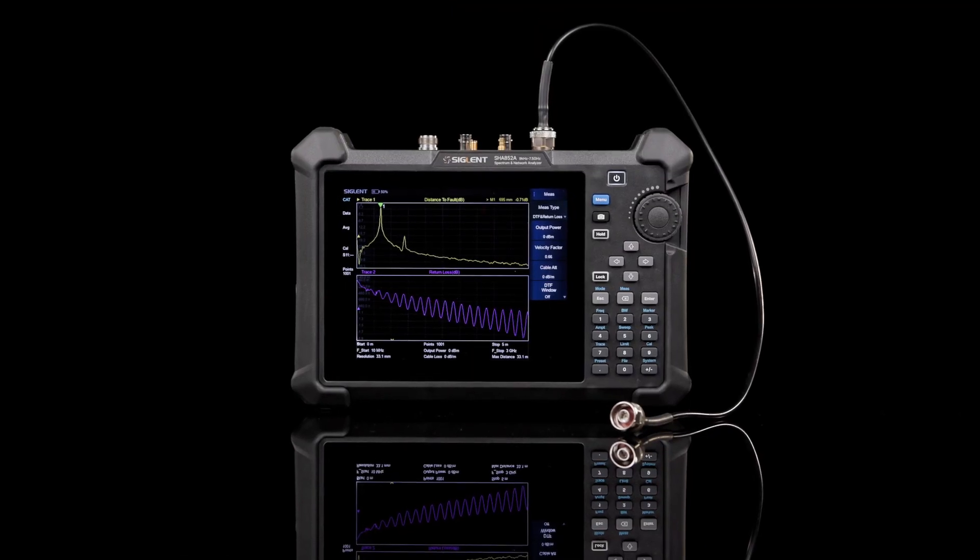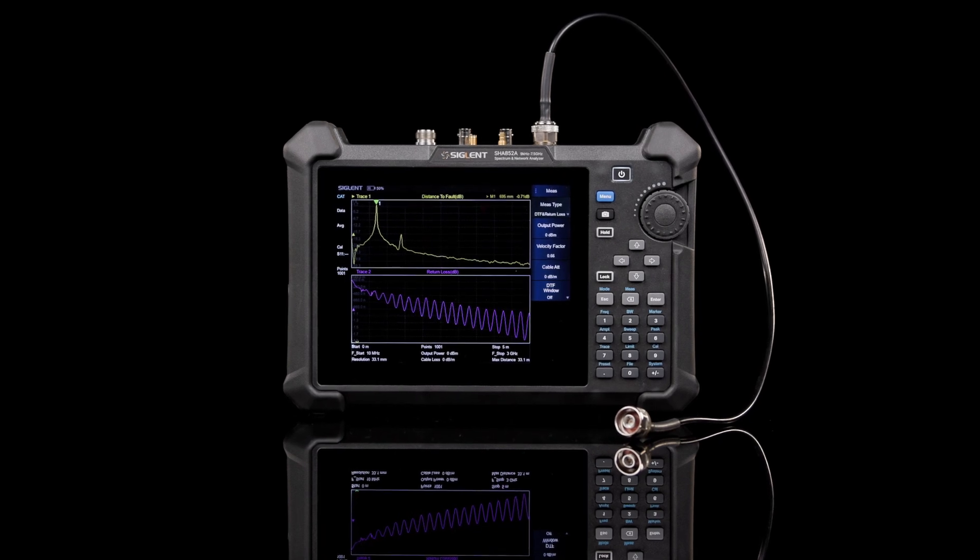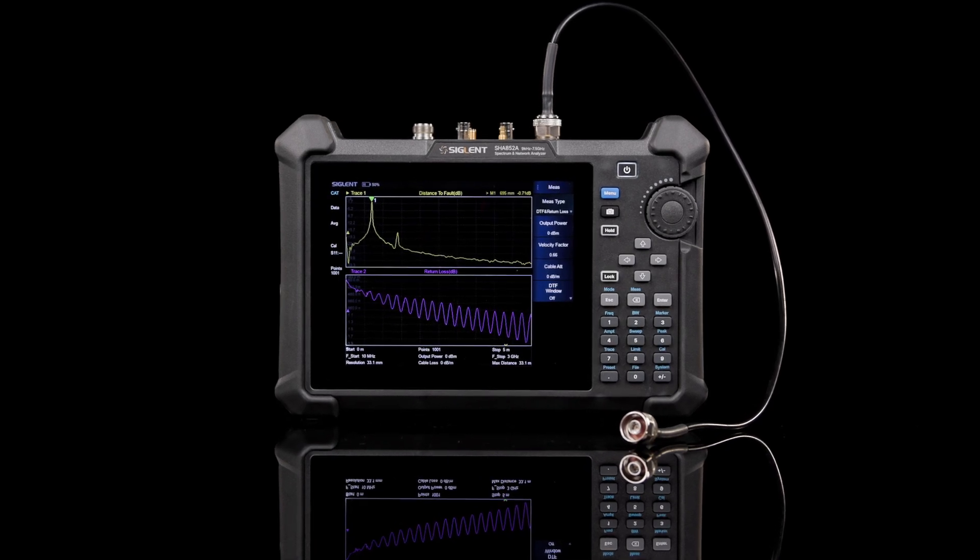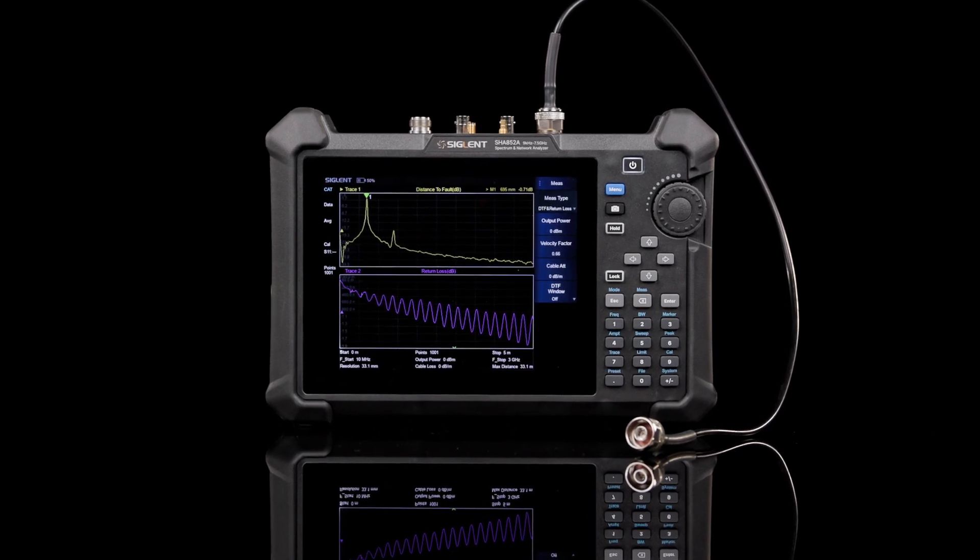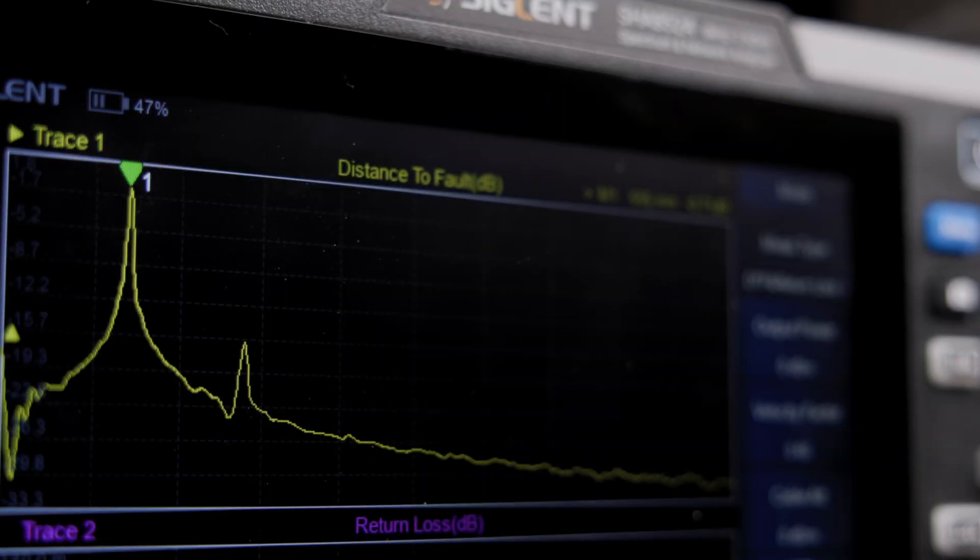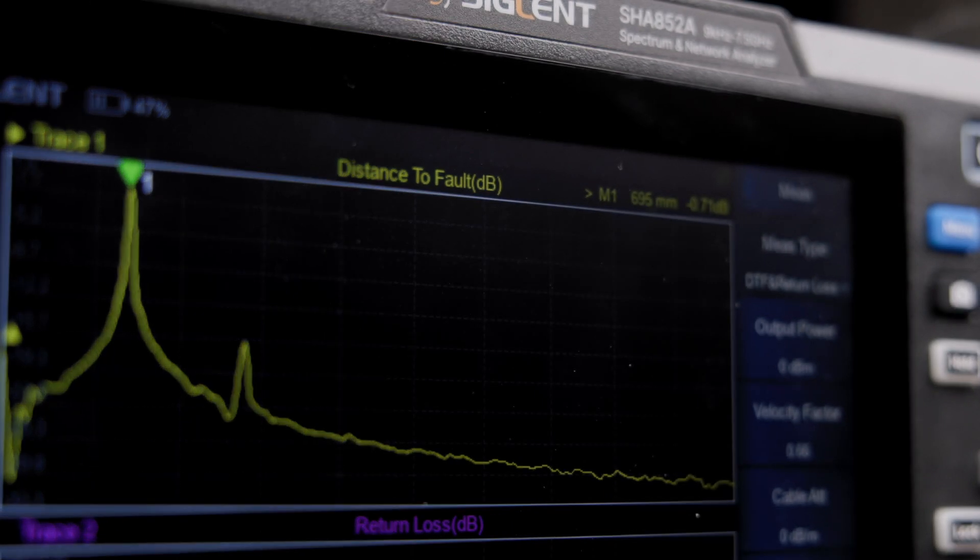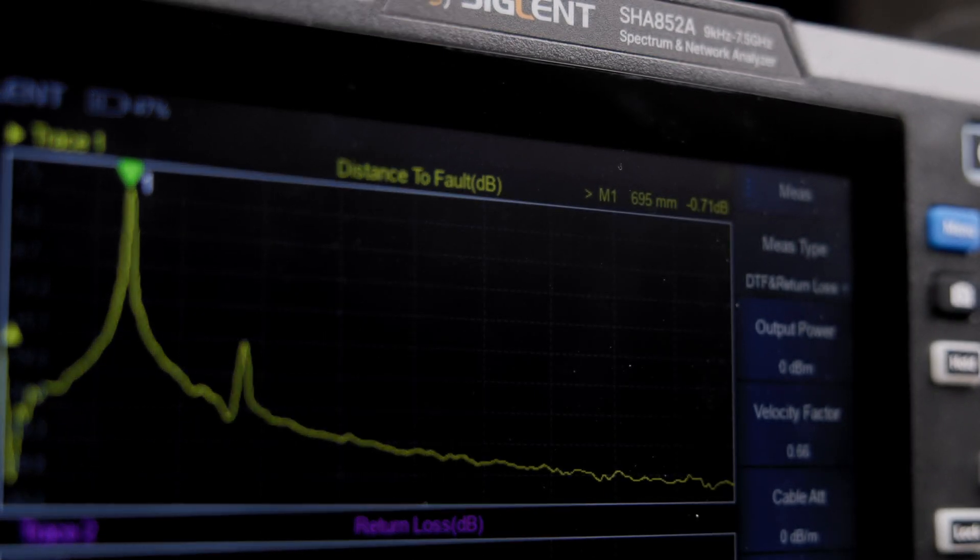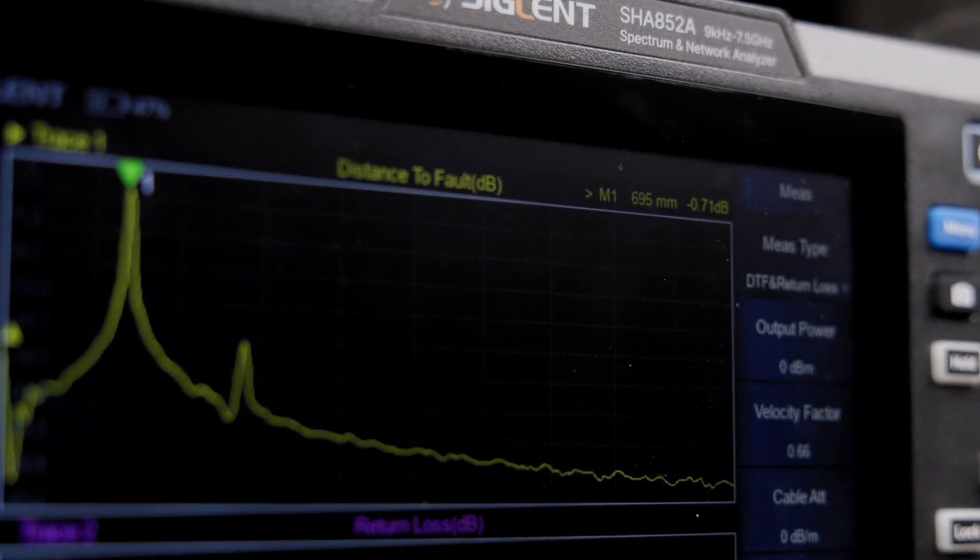Cable and antenna test mode is standard and includes distance to fault and VSWR measurement capabilities. Use this mode to locate transmission line defects and debug base station components.